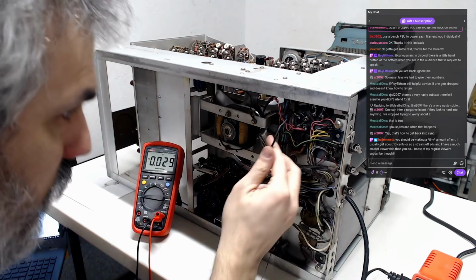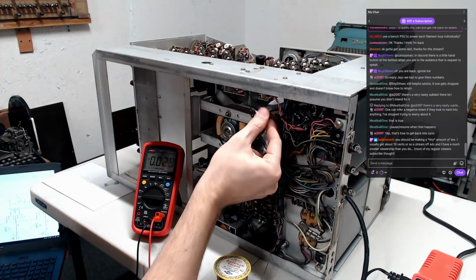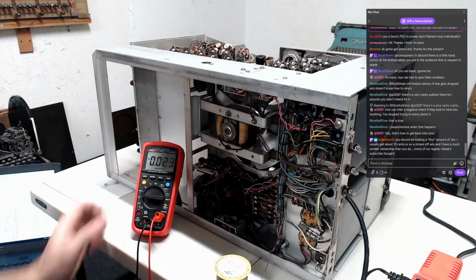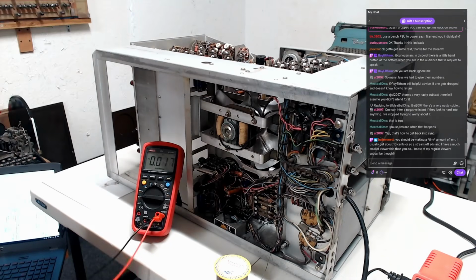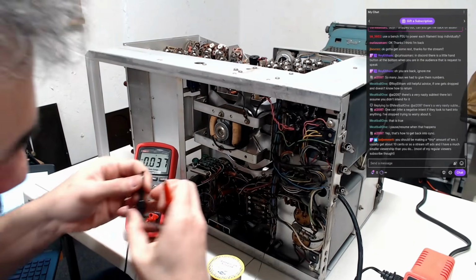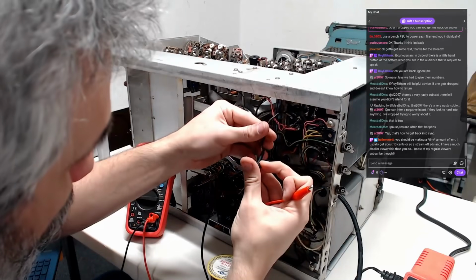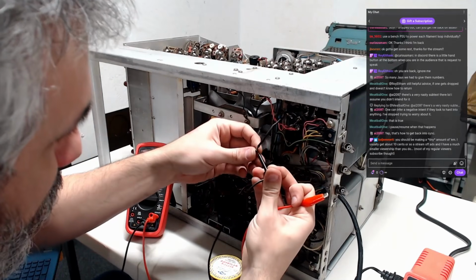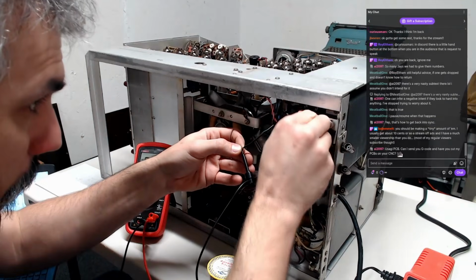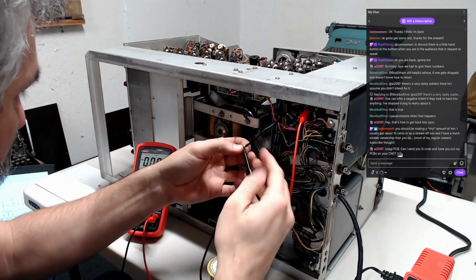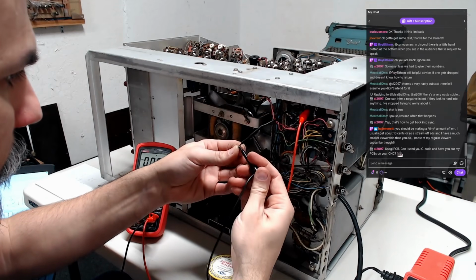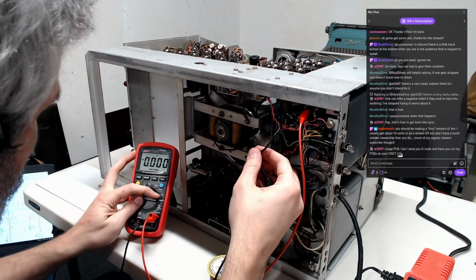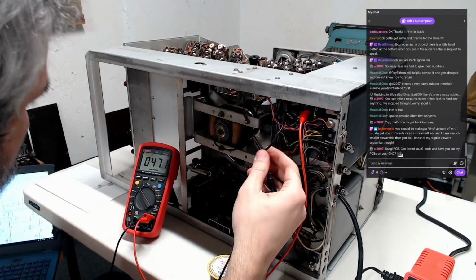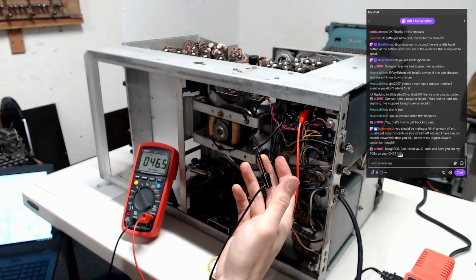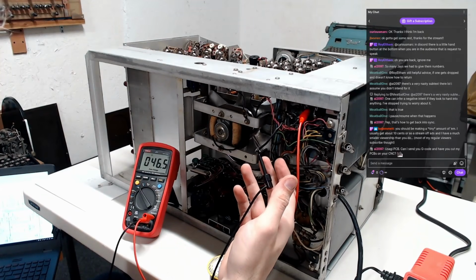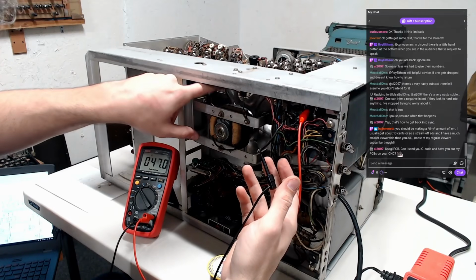All right, that's one leg of the fan removed. So what should the resistance of a fan coil be? Guess it depends on the fan. That one's 46 ohms. That doesn't sound like a dead short, that seems okay.